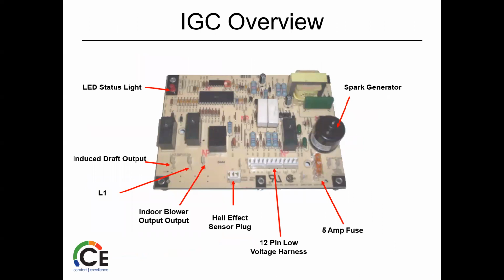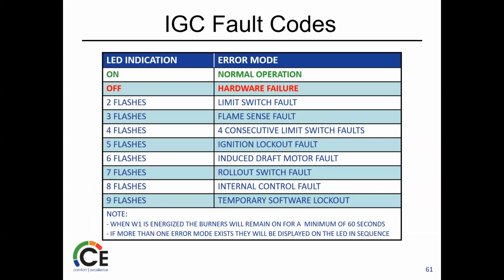So again, there's your LED status light, induced draft outputs there, indoor blower output. Talked a little bit about the Hall effect sensor. Thankfully they're sort of a thing in the past, but you're still going to run into them depending on how much commercial work you do. There's your low voltage harness, which everything ties right to the main board. It does have a 5 amp fuse. Obviously, most don't have a spark generator anymore, but some do. They're still out there. So this part hasn't changed.